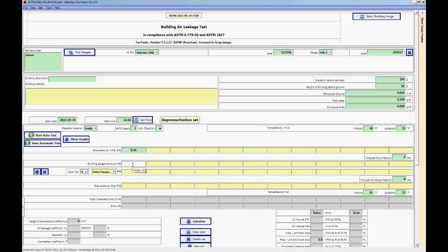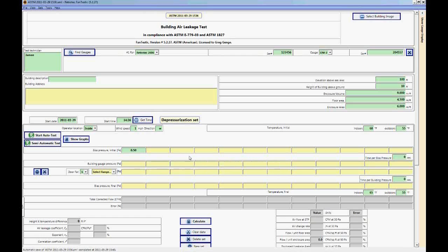So if you hover over each cell you'll notice that it is set up to take a pressure of 10 pascals, 20, 30, 40, 50, and 60. So although ASTM suggests that the building pressures are taken from 10 pascals to 60 pascals, we recommend that they be taken from 15 to 60 or even from 20 to 60 instead.